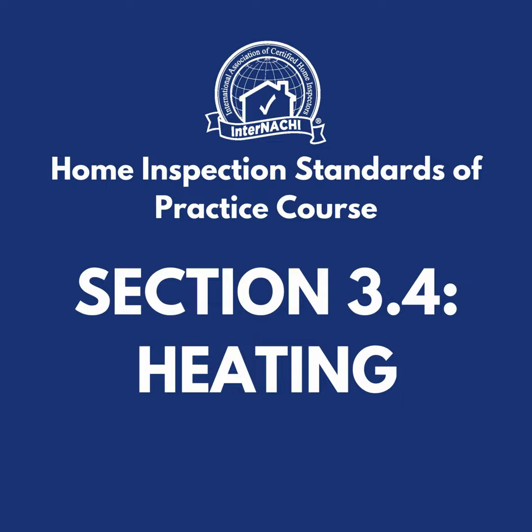Any analysis of the adequacy or efficiency of a heating unit and its distribution is technically beyond most home inspectors' ability. A heating system's performance should be evaluated by trained and/or licensed personnel. Most home inspectors check the service tag on the heating and cooling system. If there has not been any service on the system within the past 12 months, then service and further evaluation is recommended. Any system should be operated only in its normal environment, and care should be taken not to damage any system or control by inappropriate use. The inspector should return all controls to their previous settings after completing the inspection. The home inspector is not required to measure or calculate the air for combustion, ventilation, or dilution of flue gases for appliances.